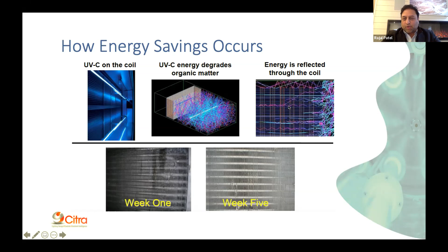We normally find 60 to 90 days to get through the entire depth of the coil. On the bottom here, we're showing a photo taken before UV installation and then 5 weeks after. So in 5 weeks, you're seeing the effects of the UV already take place. But as this cutaway image shows, it's still working its way through the depth of the coil.